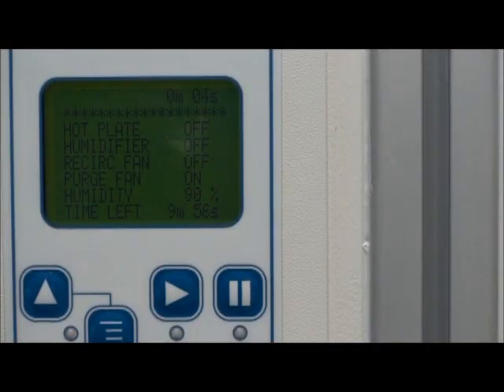Once the vaporization time is completed, the cabinet will go into purging. The purging time will be what you've set, which we did 10 minutes on this one earlier on, just for this demonstration period. At the end of that 10-minute period, the fumes will have gone and the cabinet is safe to open.